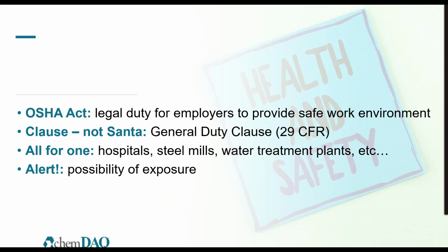So you might as well not only protect your employees' health, but protect yourself and the company that you work for. I will also mention some of the other standards that are out there. 8 hours is the most common. There's also a 15-minute time-weighted average that is included in some, and that's going to be their average exposure over a 15-minute time frame. And there is also an IDLH, which is immediately dangerous to life and health.